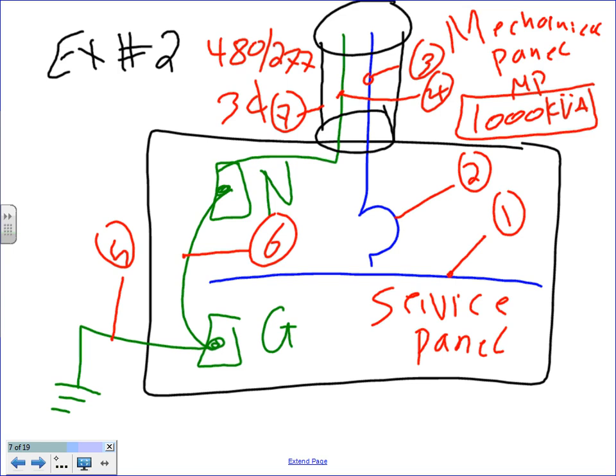They're rated in horsepower. So what we do is, if it's a 15 horsepower motor, you take the amps from the code, multiply it by 1.73 because it's 3-phase, multiply by the voltage, which is the nominal voltage we use, 480, add them all up, and you end up with a demand of 1000 kVA. You guys have done this when we did the calculation for the mechanical panel. Any questions about the kVA? That's what we calculated.